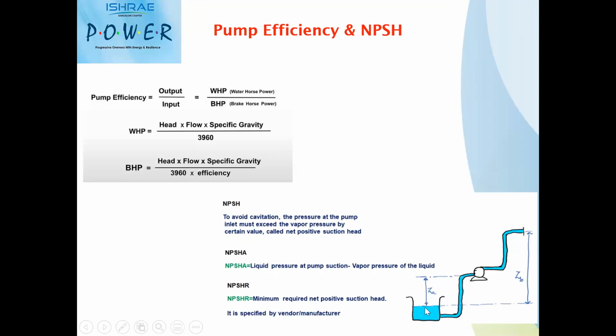If you see any pipe with this typical arrangement, you can see that the water column is rising because the atmospheric pressure keeps on acting on the water column. So that 10 meters is always available on the suction side due to atmospheric pressure. Any losses on the suction side of the pipe plus the vertical height which the water has to travel has to be deducted from your atmospheric pressure to get the net positive suction head available on the suction side of the pump.